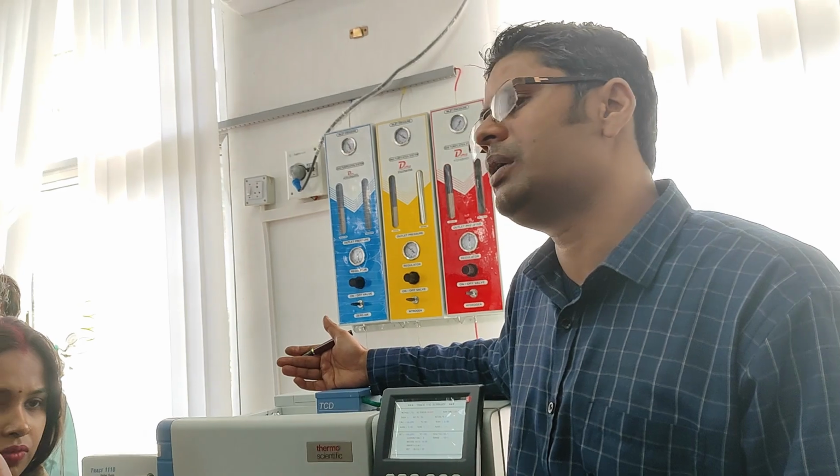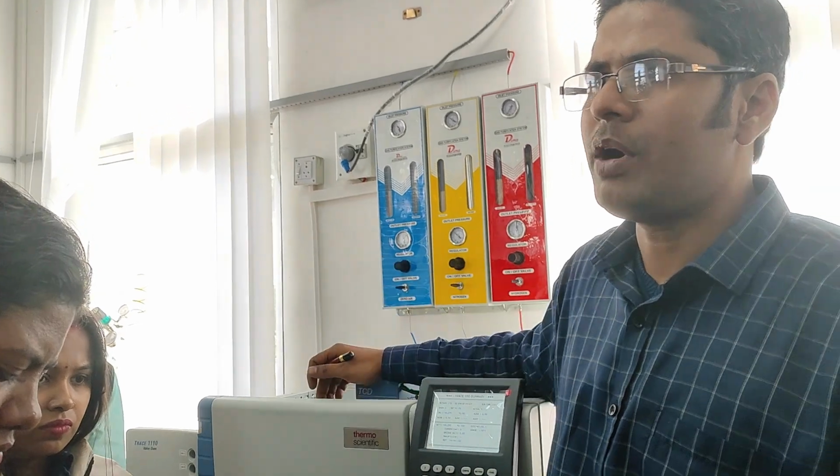I already told you these gases can be done. If your sample contains these gases, you can use it, because GC is a very vast application instrument. Many institutes and industries use GC, with different applications like transformers in the power sector and power plants. A big transformer has insulating oil inside. They regularly check the health of the transformer by extracting the gases from the insulating liquid. That liquid oil is taken from the transformer into a gas extraction apparatus.